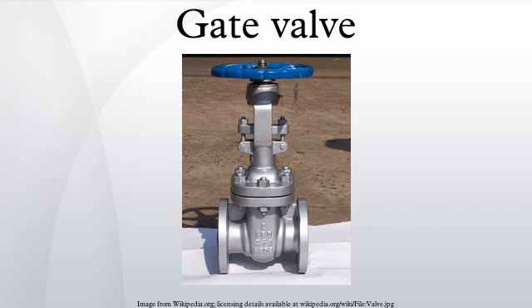Gate valves are characterized as having either a rising or a non-rising stem. Rising stems provide a visual indication of valve position because the stem is attached to the gate such that the gate and stem rise and lower together as the valve is operated. Non-rising stem valves may have a pointer threaded onto the upper end of the stem to indicate valve position, since the gate travels up or down the stem on the threads without raising or lowering the stem. Non-rising stems are used underground or where vertical space is limited.